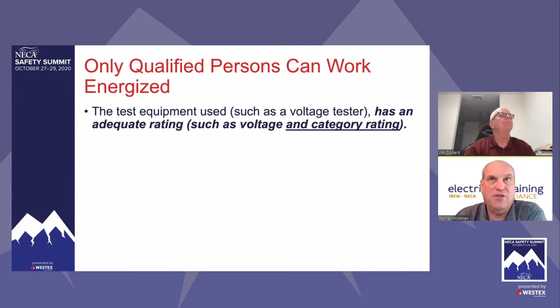So back to Jim's point, are you a qualified person for verifying absence of voltage on a 5 kV branch circuit? Let's say there's a chiller and you have to shut it off. How do you verify absence of voltage? Well, if you're getting your 600 volt tester out, you are not qualified. You better be getting a hot stick out and putting a proximity meter on the end of it. So just things like that.